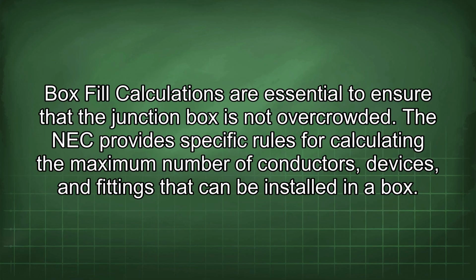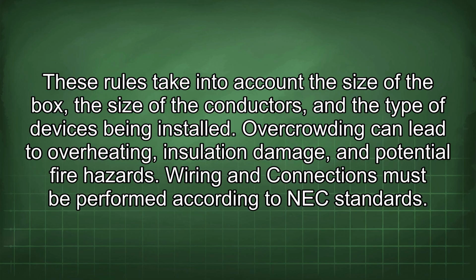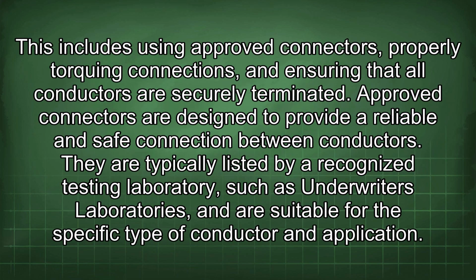Box fill calculations are essential to ensure that the junction box is not overcrowded. The NEC provides specific rules for calculating the maximum number of conductors, devices, and fittings that can be installed in a box. These rules take into account the size of the box, the size of the conductors, and the type of devices being installed. Overcrowding can lead to overheating, insulation damage, and potential fire hazards. Wiring and connections must be performed according to NEC standards. This includes using approved connectors, properly torquing connections, and ensuring that all conductors are securely terminated.